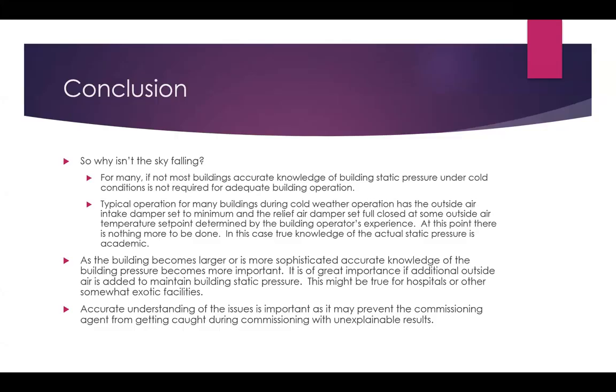Next question, they're asking, what about the pressure drop through long runs of sensor tubing being greater than the static pressure you are trying to control to? So pressure drop is a function of flow. And you actually have almost no flow even through 1/4 inch tubing. So I would not envision any pressure drop concerns through long tubing.